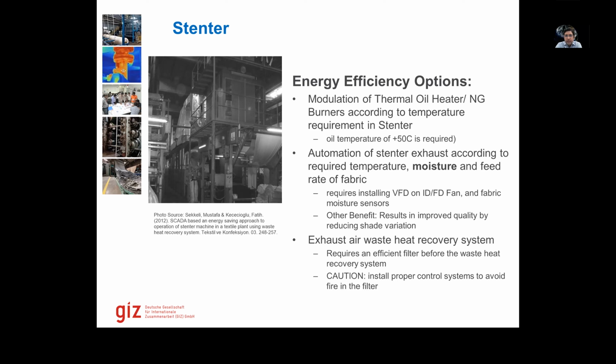So if we need 150 degrees Celsius inside the stenters, the oil should be heated up to 200 degrees Celsius. What I have often seen is factories heating up oil to between 250 and 300 degrees Celsius, while the processes are using heat from 120 to 150 degrees Celsius. That means we are putting in too much energy in heating up the oil. And this we can see at the oil heater.